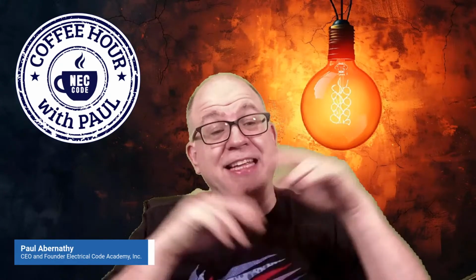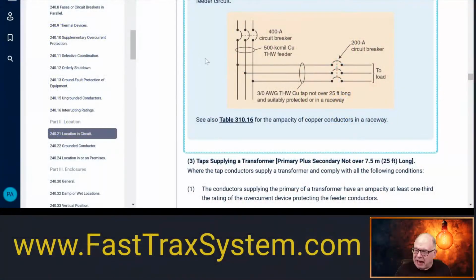I think one of the key takeaways for this 25-foot tap rule is that, again, if I want to come out of that 400 amp device and take my tap conductor straight to the lugs and utilize the tap rules, then I can do that. But what people forget is, this is great, let me bring you back to this. Let me show you. This could blow people's mind. If I wanted to come out right here, and if these conductors right here were the same size as these conductors, then guess what? This is not a tap rule. That would be just part of the feeder. In that case, you run into an issue right here.